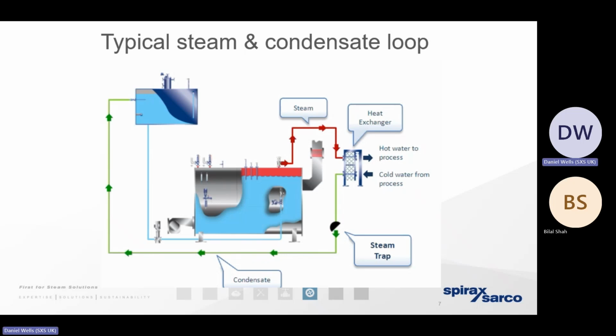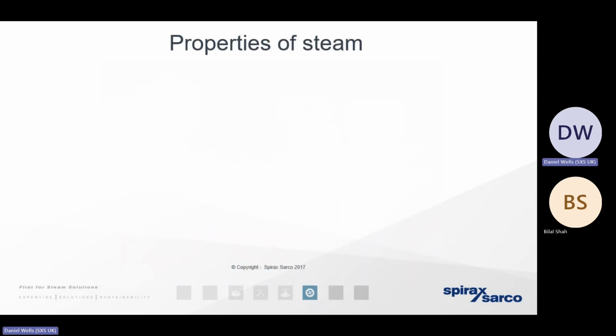So that's why we've got the term loop. Steam as a gas with a high energy density leaving the boiler, moving towards the heat exchanger, the condensate as a liquid with a very high temperature coming back. So when we think about a steam boiler house or a steam distribution system, we need to remember the differences that steam has compared to a traditional hot water-based heating system. And we need to ensure that the system is designed accordingly.